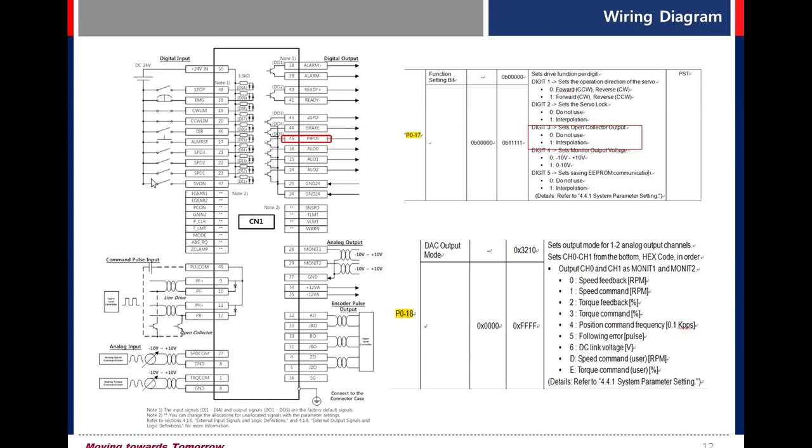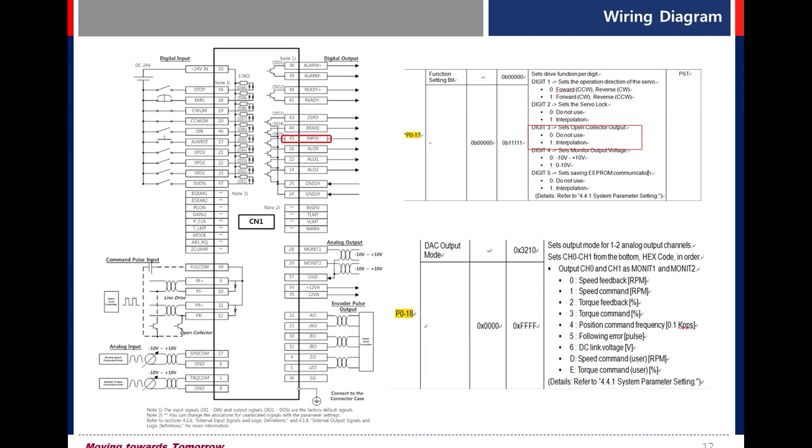Alarm group 0, 1, 2, 3. Through combination of those contacts, it presents which alarm group triggered. For example, alarm 2 off, alarm 1 off, alarm 0 on, 10th alarm triggered. Also, you can use this function for open collector output. To use this function, you have to set P017 digit 3, the value 1.